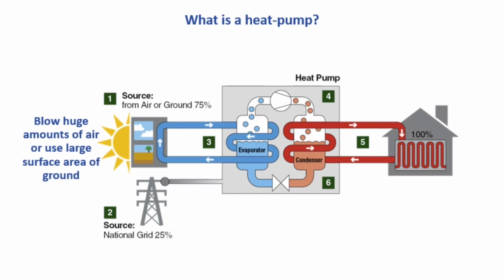It's all the same principle, and whatever the source is, whether it's air or whether it's water glycol flowing through the ground, it exchanges its heat, the air by a blower or the pumped water from underground, with an evaporator, which is a heat exchanger, to the refrigerant. It boils the liquid in this evaporator as it's going into a heat pump compressor, which is this circular item here. And the compressor takes gaseous refrigerant and raises its pressure. And as it does so, it raises its temperature, as we saw earlier with the piston of air.